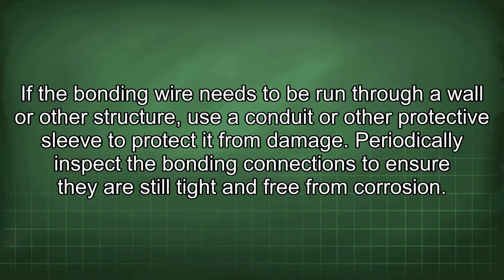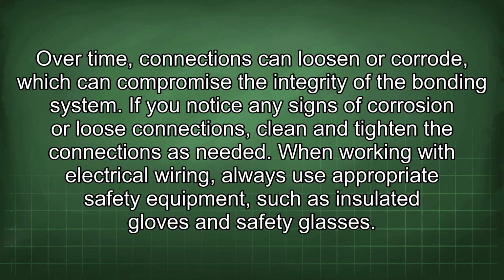Periodically inspect the bonding connections to ensure they are still tight and free from corrosion. Over time, connections can loosen or corrode, which can compromise the integrity of the bonding system. If you notice any signs of corrosion or loose connections, clean and tighten the connections as needed.